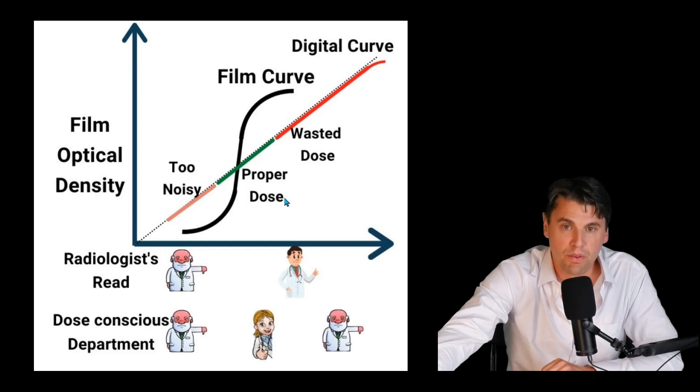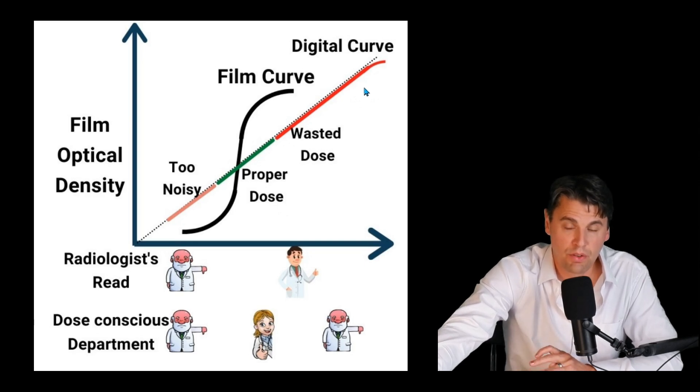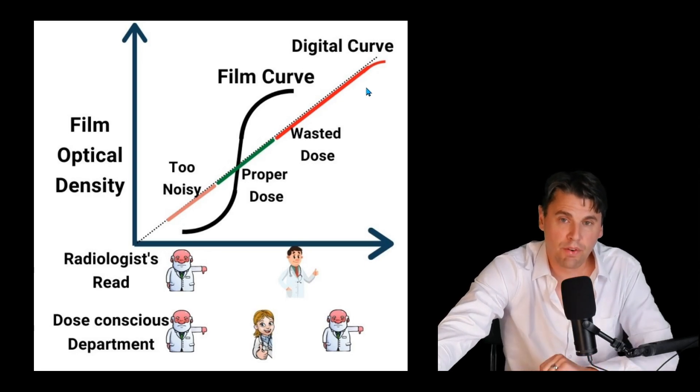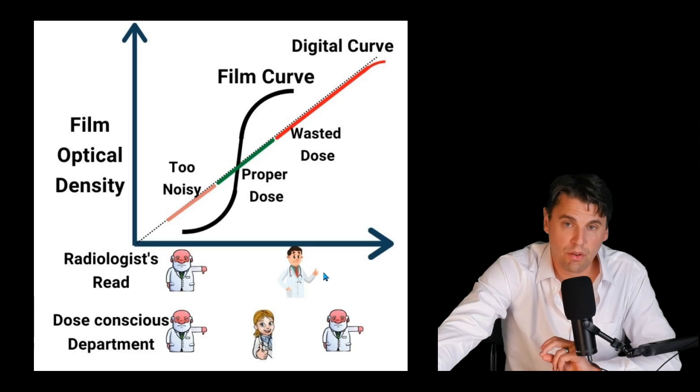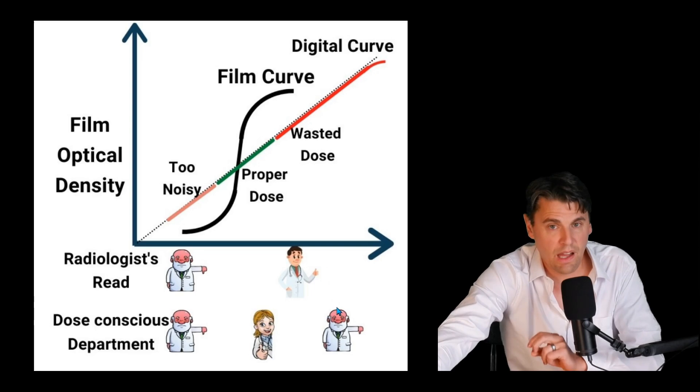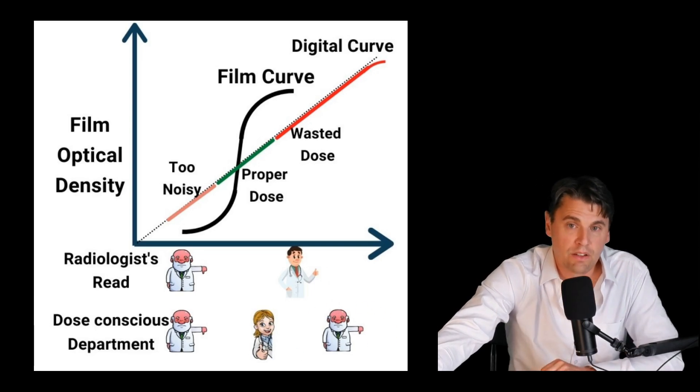From that perspective, it's good. The radiologist is going to be good with looking at those images because they're not going to be saturated. However, the downside is that there's now not a built-in monitoring situation anymore. Before, the film was monitoring us because we wouldn't actually be able to make a good image if we were outside of this range.